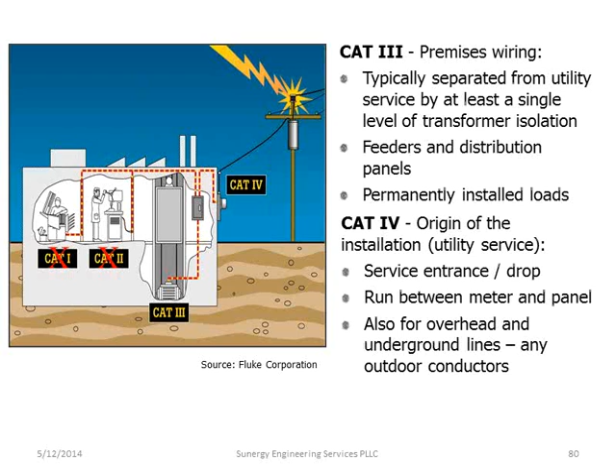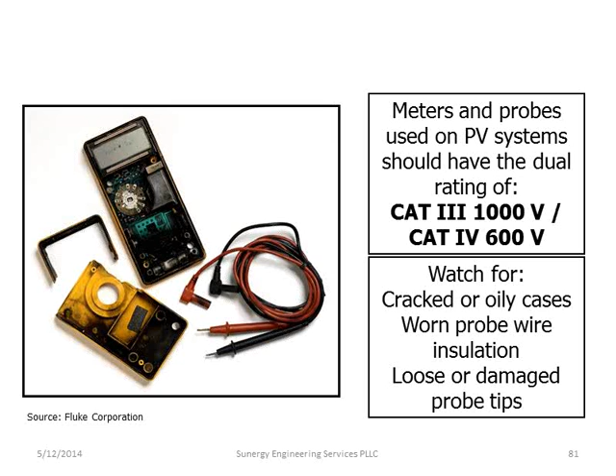This is a case where someone took a reading of a 600 volt DC array with a Walmart special meter that didn't have the rating, and it arc faulted and blew up in his hand, causing major burns. If you go on the Fluke website, they've got a great page about using the right equipment when you're doing tests like this.